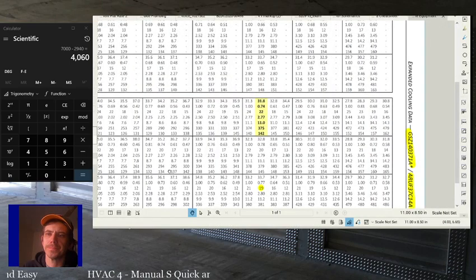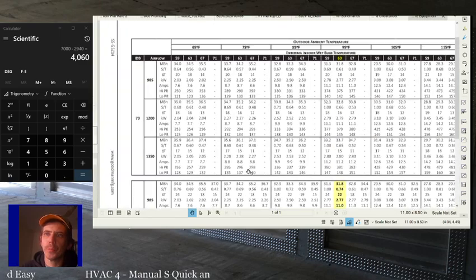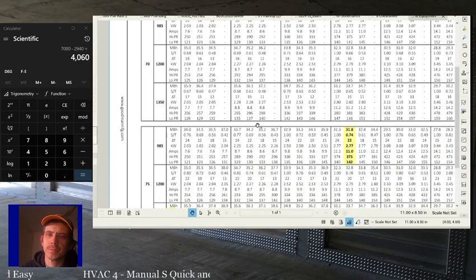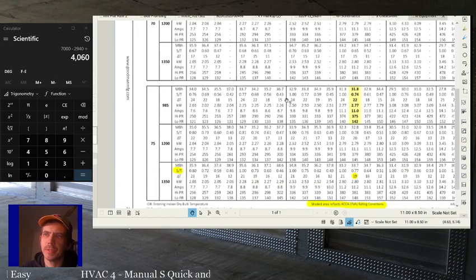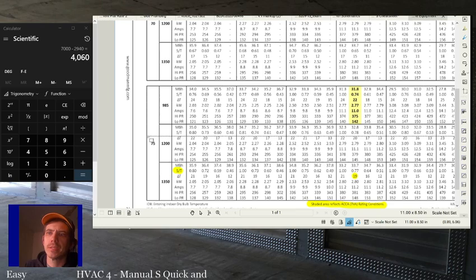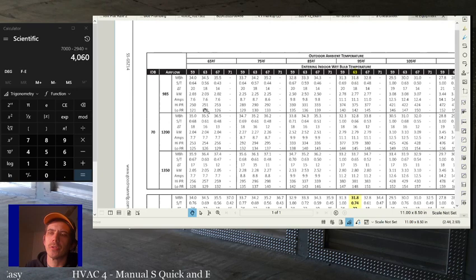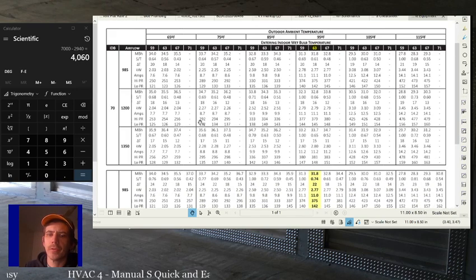So again, when you're picking your equipment, especially in Fairfax, Virginia, right? But this could change a little bit where you live, but a lot of these numbers stay the same. One of these numbers that stays the same is the 75 degrees inside. You always pick your cooling equipment at 75 degrees inside. The other thing that should probably never change, it can if you want to design at different humidities, but in general you design at 50% humidity, so it should be a 63 degree wet bulb inside.